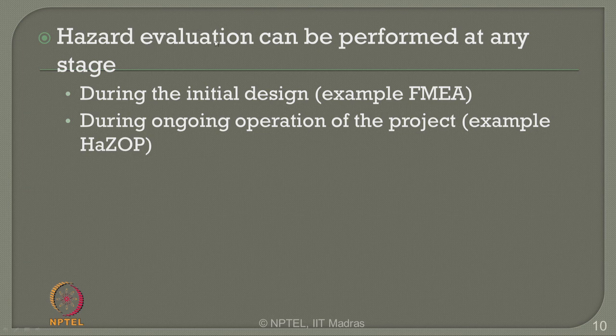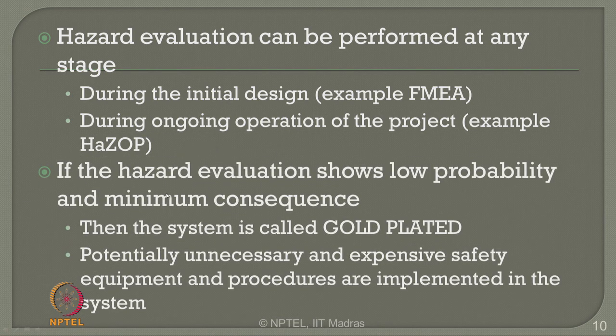Hazard evaluation can also be done in a plant during ongoing operation. An example is HaZOP study. If the hazard evaluation shows low probability and minimum consequence, then the system is labelled as a gold plated system. Unfortunately, you must understand that a gold plated system always has potentially unnecessary and expensive safety equipment and procedures in place, which are implemented in the system. So, the system otherwise becomes very expensive to maintain, to remain as gold plated.